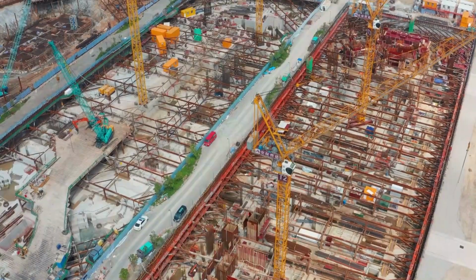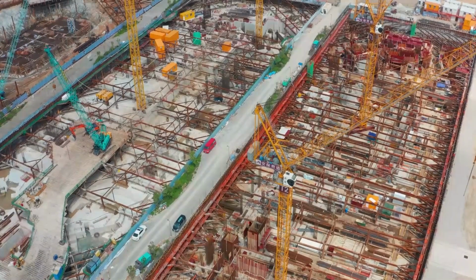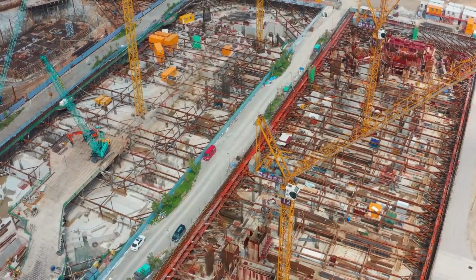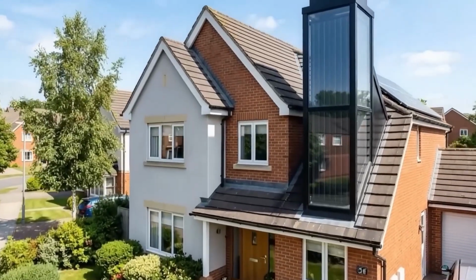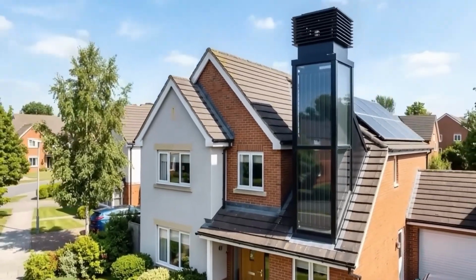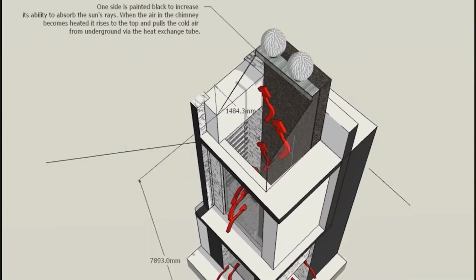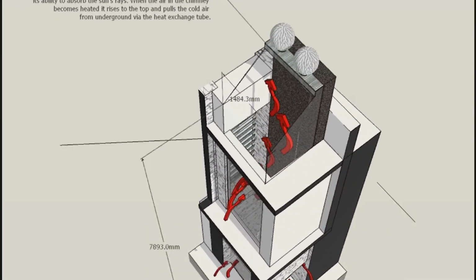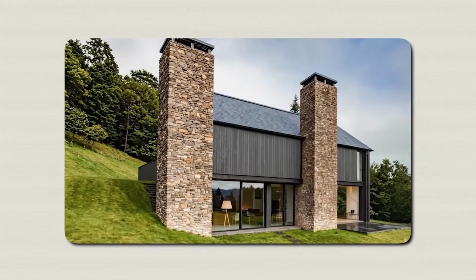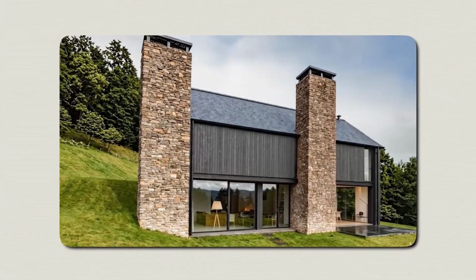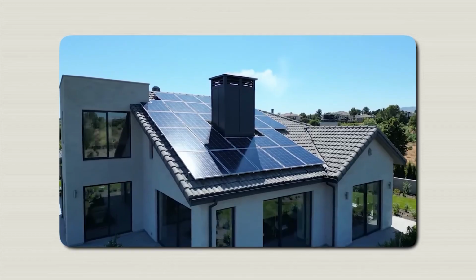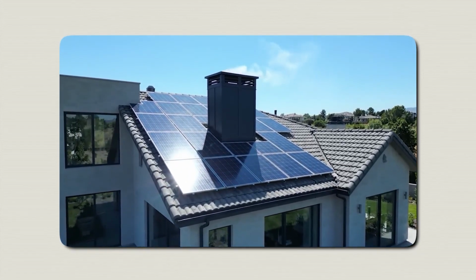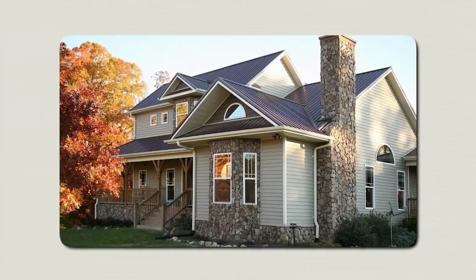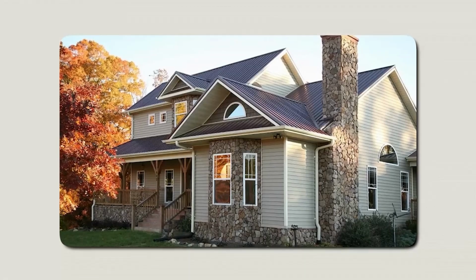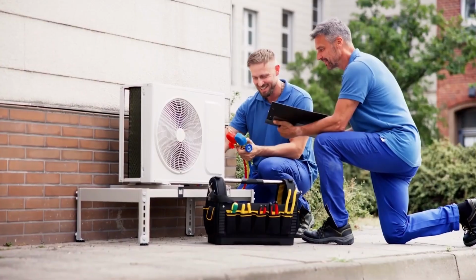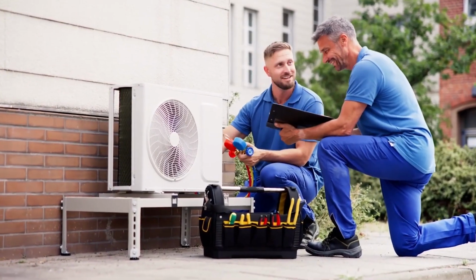For new construction, the optimal approach is to design the earth tube as part of the building's passive system from day one, pairing it with a solar chimney at the exhaust point, positioning intake and exhaust to maximize the pressure differential, and running the pipe beneath the building's thermal mass. This is the configuration Lee and Strand's research identified as delivering the highest performance: a self-reinforcing loop where the chimney provides the suction and the earth provides the cooling, entirely without mechanical input.